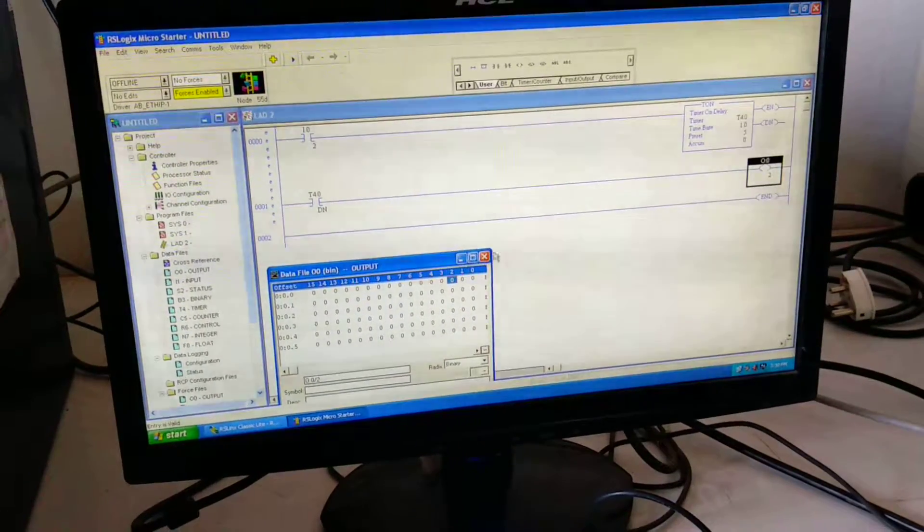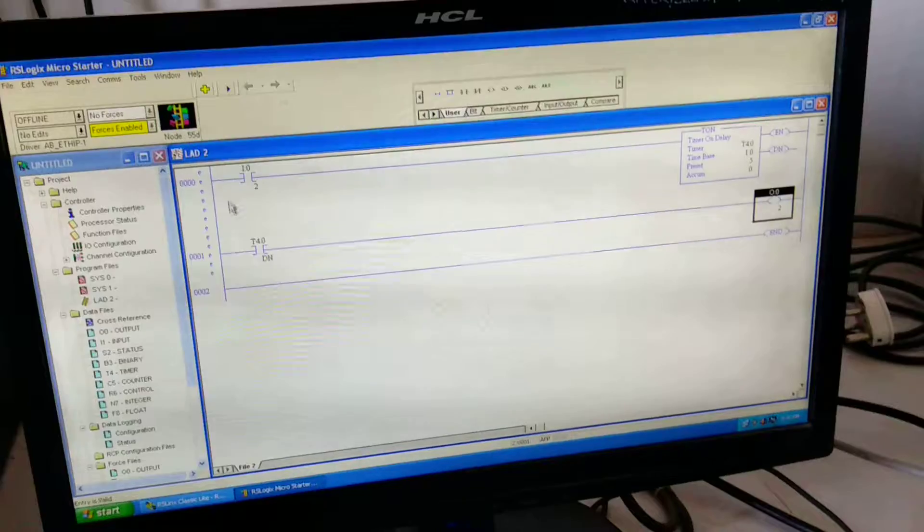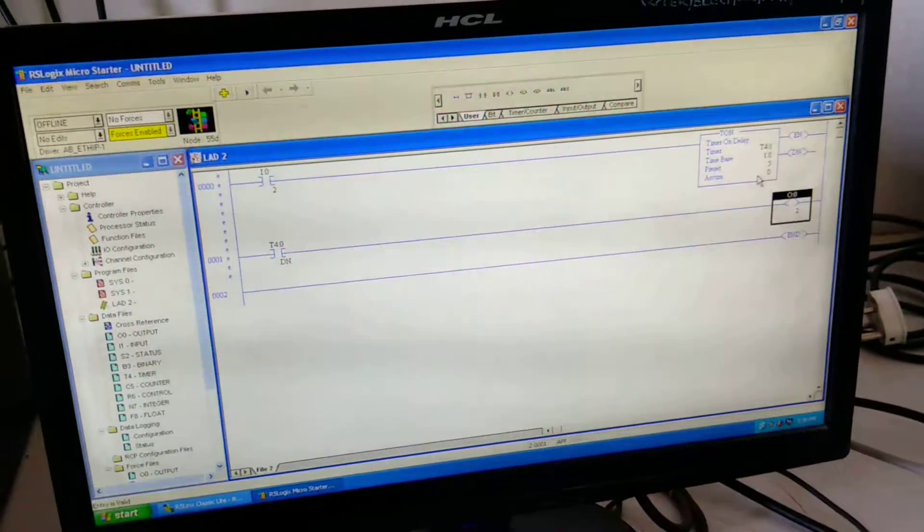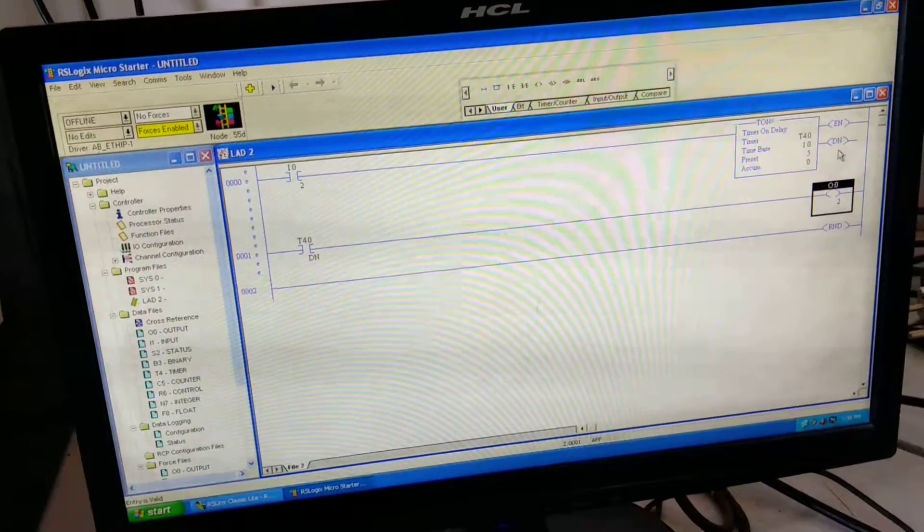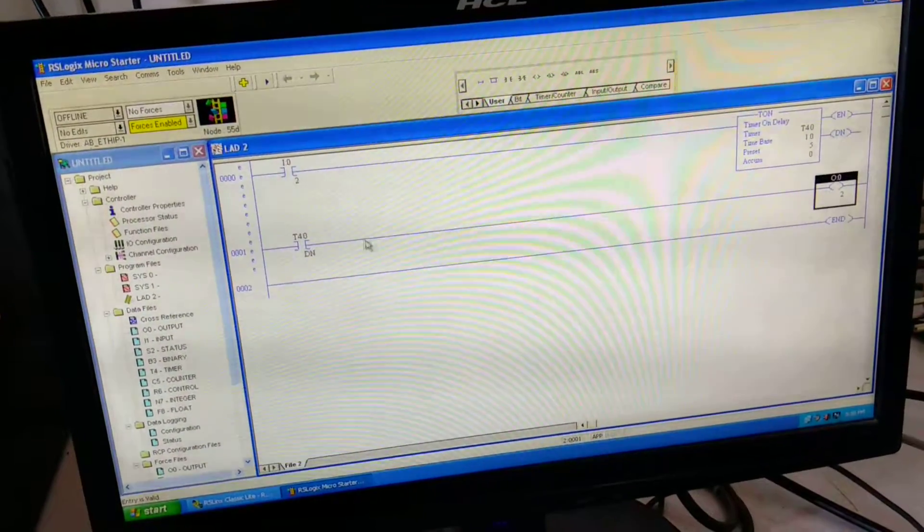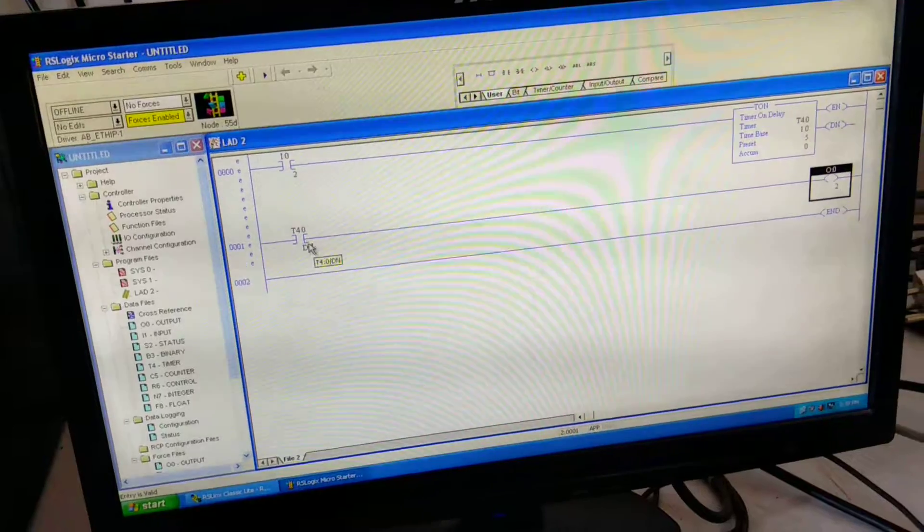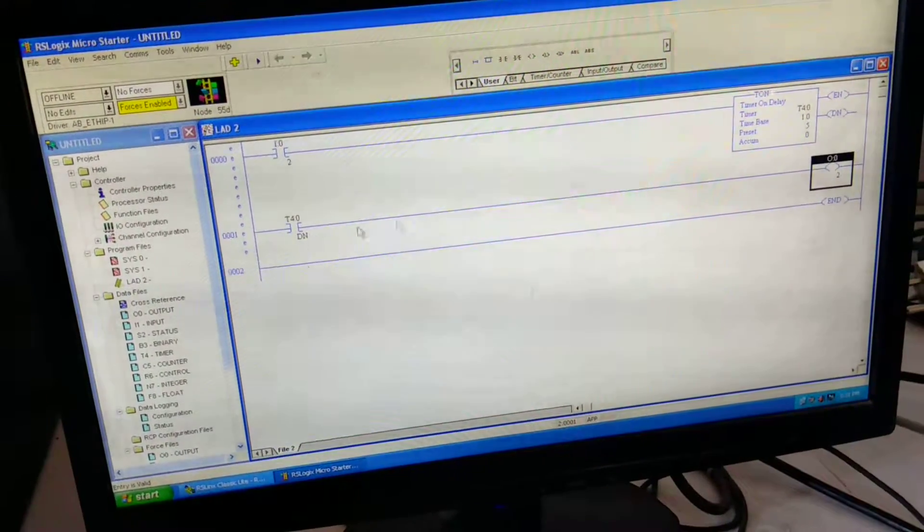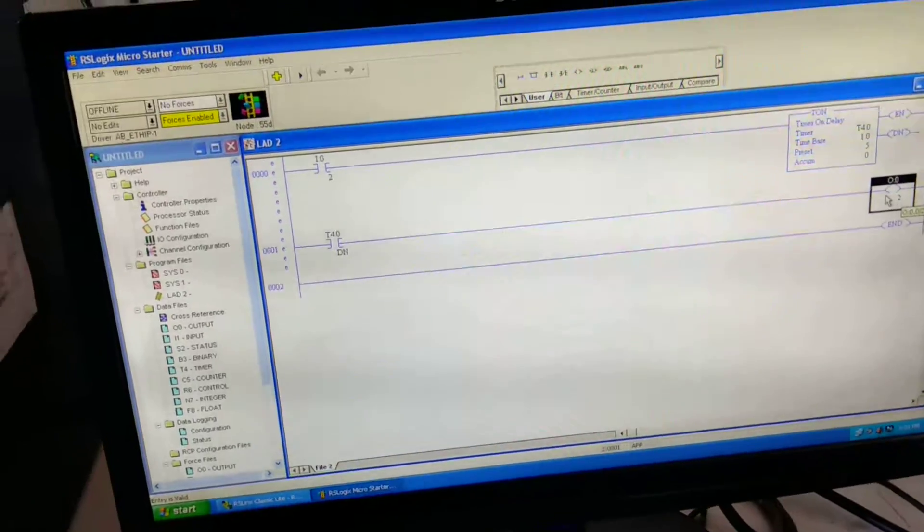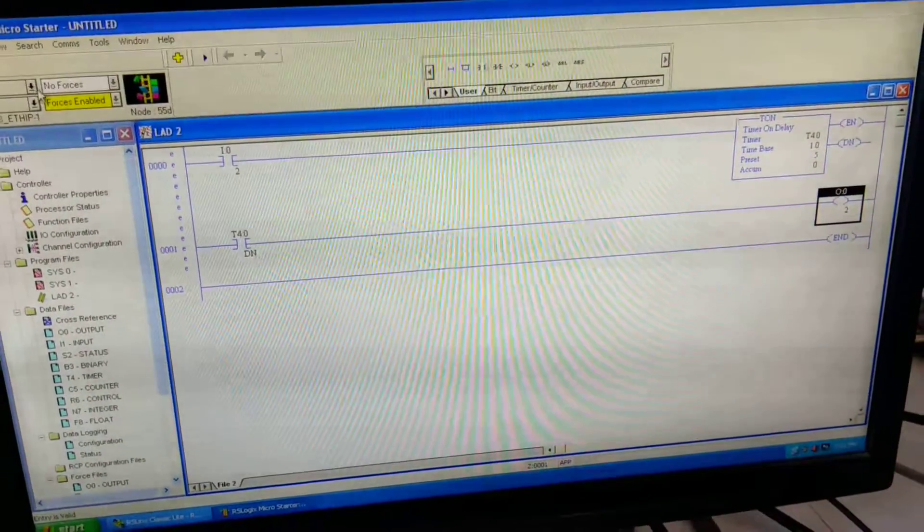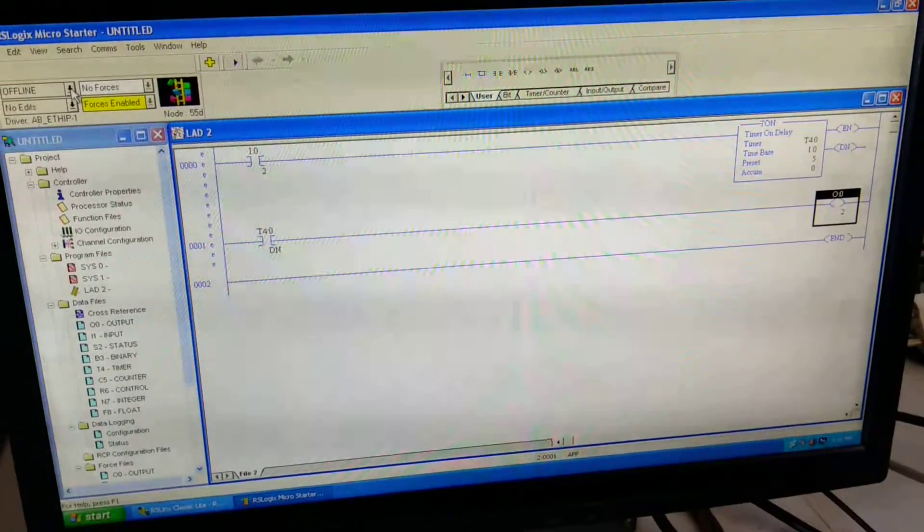So whenever we will operate the input I:0/2, our timer will start. Then the done bit of timer will get activated after 5 seconds. That will be given input to the T4:0 done, and that is given to the output lamp. So our lamp will glow. For that we have to download the program.